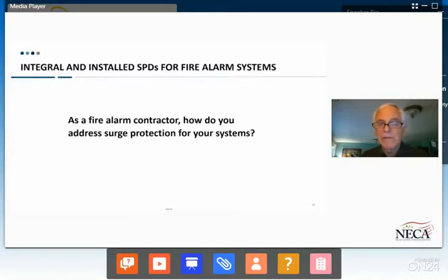When they don't include it, we purchase it separately. For equipment that's supplied from a Class 2 power supply, like a plug-in transformer, we typically interpose a Type 3 surge protected plug strip or similar device where we can to protect those systems. We know that many of the products that we purchase are manufactured with internal surge protection of the MOV type, which is integral to the device, but because of the sacrificial nature of MOVs, we don't consider those to be adequate for the protection of this type of system.